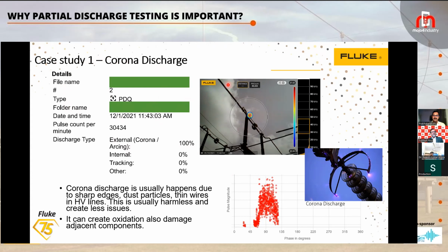Here you can see the picture of the image, and also the artificial intelligence through which it will analyze and then show you what kind of partial discharge is present in that. In this picture, it is showing the complete partial discharge is through corona. That means there is no other partial discharge. It is only the corona, and it can be taken easy, because usually the effect of corona is much lesser, and it is usually neglected in our industry.